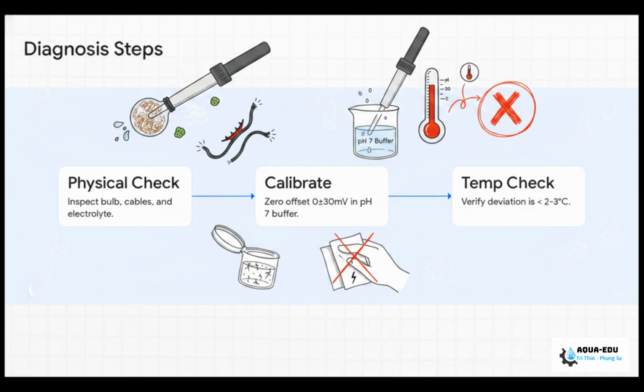Then step 3 is your calibration check. Rinse the probe with distilled water, and here's a massive pro tip straight from the manual. Never, ever wipe the glass with a paper towel. It creates static electricity and ruins the reading. Just put it in a pH 7 buffer. We want to see a zero offset of 0 plus or minus 30 millivolts. For step 4, check the temperature. Compare the probe's temperature reading against a real thermometer. If it's off by more than 2 to 3 degrees Celsius, that built-in temperature sensor has definitely failed.